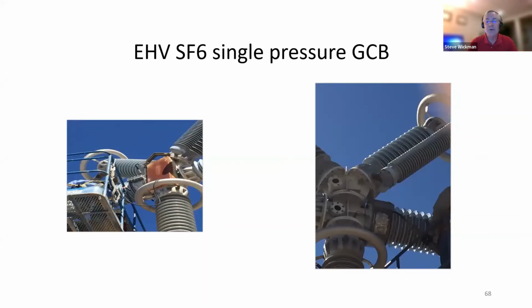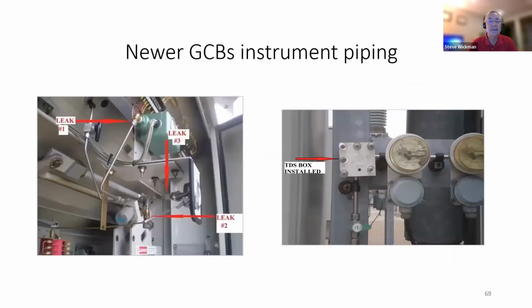EHV single pressure newer vintage breakers. There's again another steel to porcelain flange up here. Kind of really tough to make these out. It's in the shadow there, but there is a clamp that was put on up there, filled with the sealant compound to contain the SF6 from leaking out on these guys.